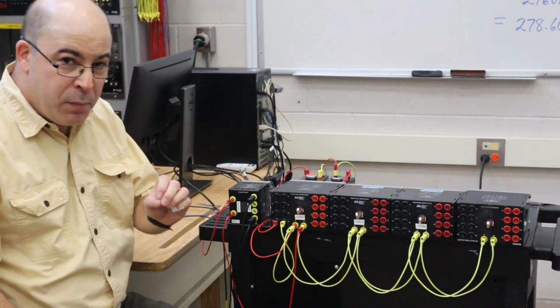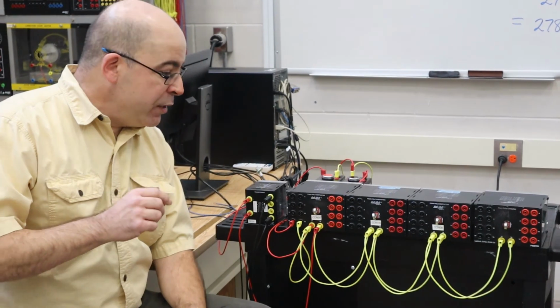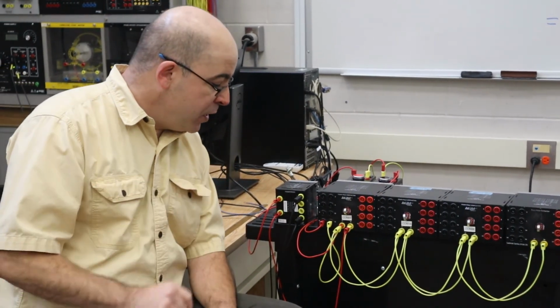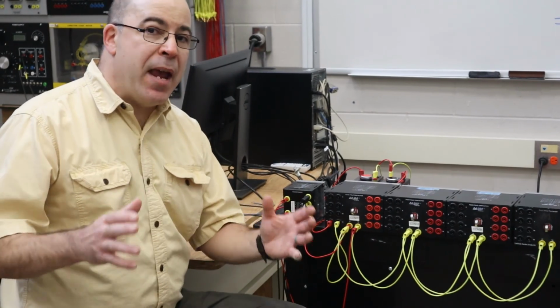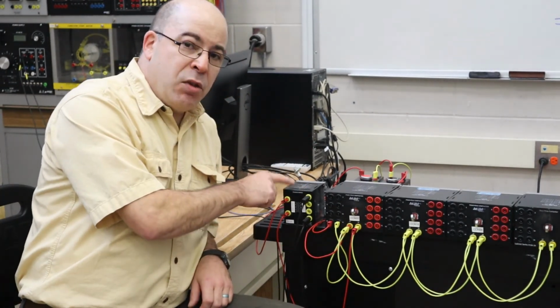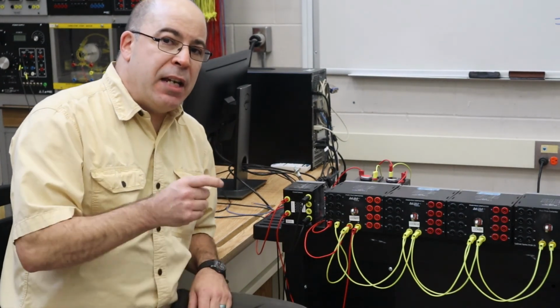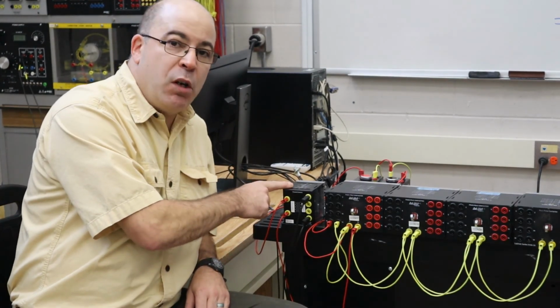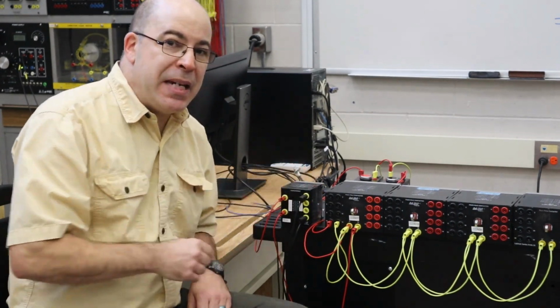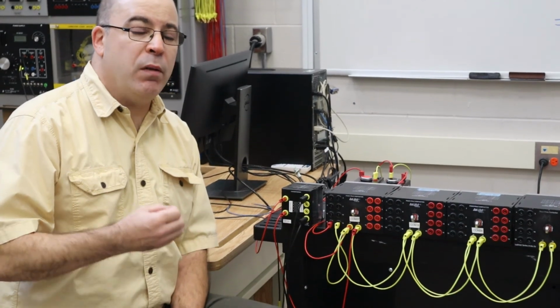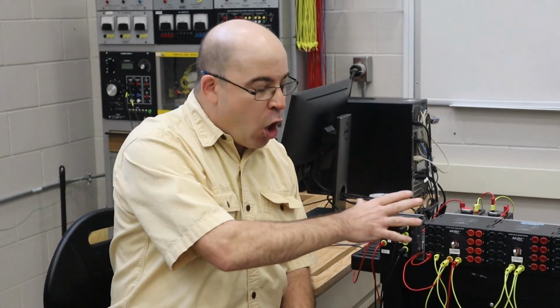And this is where it brings up that last note. When we are trying to draw more current from the transformer than it was designed to, according to your manufacturer, I'm not saying the transformer can't do it, but what's happening is that you're going to shorten the life cycle of this piece of equipment. If the transformer is humming, it means that it is starting to struggle to provide you with all that apparent power, meaning true power and reactive power, to feed all of your devices. And that's one of the biggest things that we have to look at. It's our responsibility as electrical workers to properly size our equipment so that we can ensure the longevity of the equipment that we're putting together.